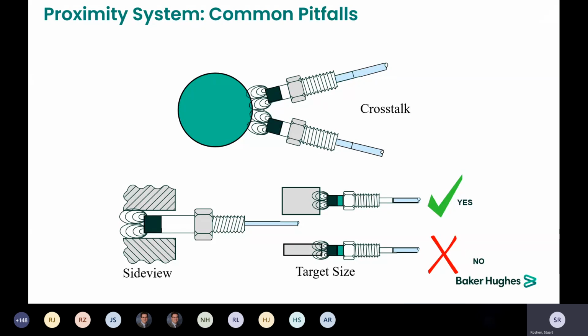I had a customer that was retrofitting thrust probes on a machine. They found a nice flat machine surface and they built their bracket, but what they didn't think about was that machine surface was over the bolt holes for the coupling, and as soon as they rotated a couple degrees, a bolt hole passed under what was supposed to be a thrust reading, thus invalidating the thrust. So they had to relocate it to a different spot. It was just one of those "didn't think about the machine actually rotated" moments.